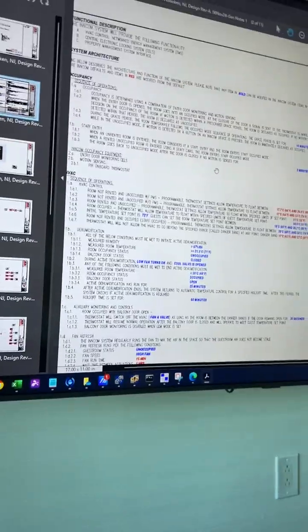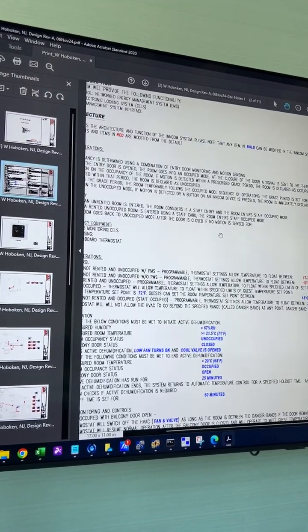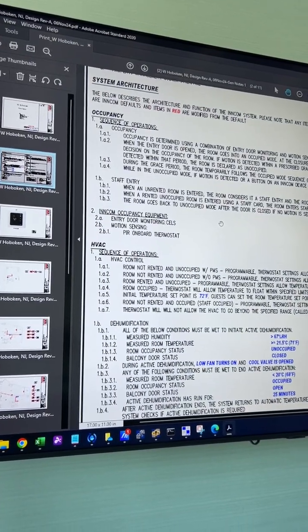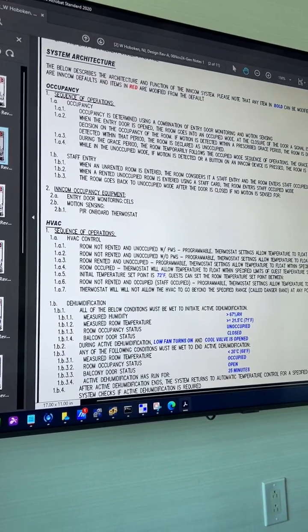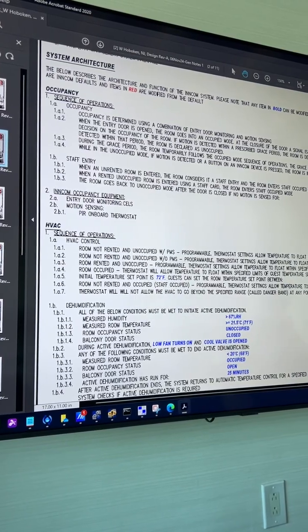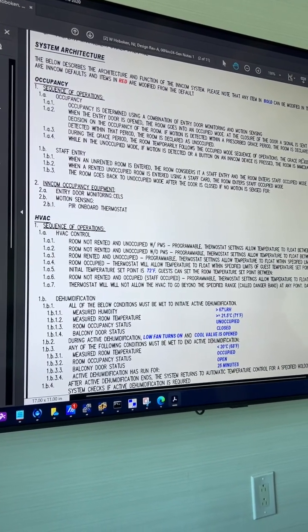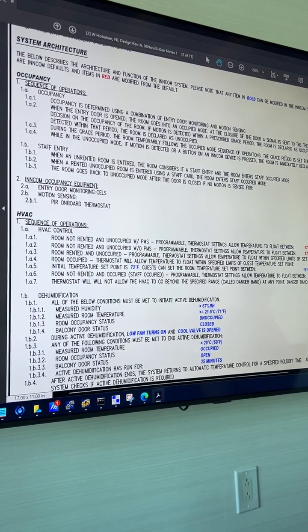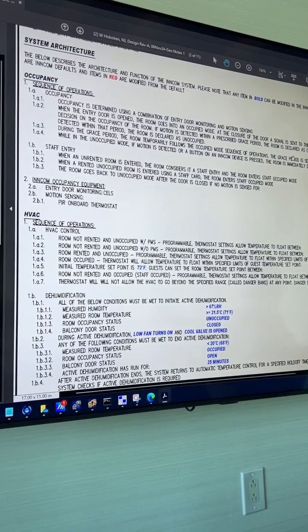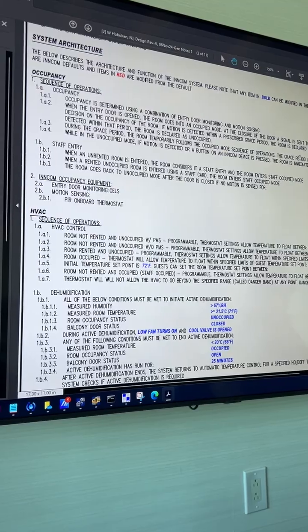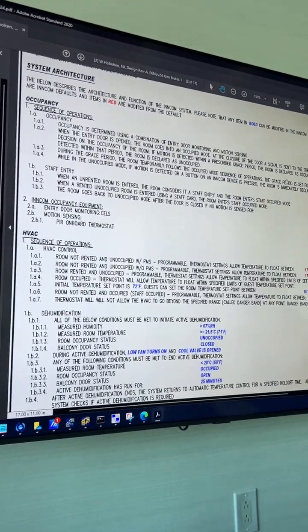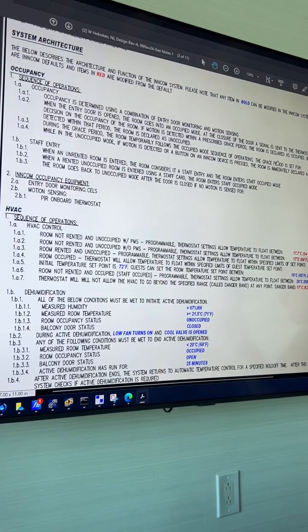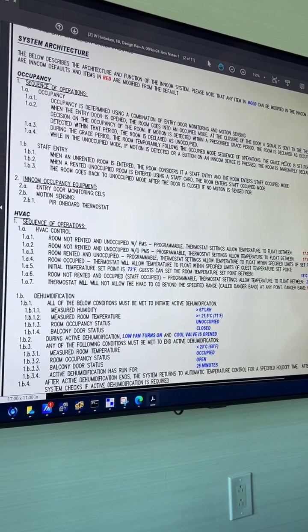Yeah, so this is going to be using the INNCOM software. I guess, real quick while I've got it open, what we're looking at here is just our sequence of operations. So, once the door is connected, door opens and closes. If no motion is detected within a 10-minute period of the door opening and closing, the room is now considered unoccupied. Okay. So, door closes, and no motion is detected after that point.